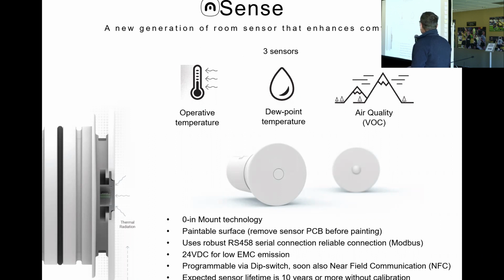To do radiant cooling, it's important to be able to evaluate the dew point temperature in a very accurate way. To do that, we have another sensor that measures two things: the air temperature and the air humidity.